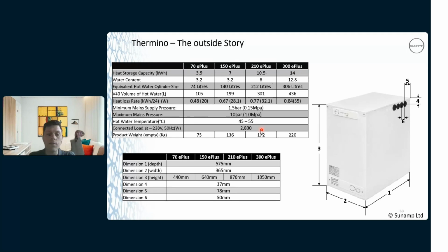Our units, I've got a 2.8 kilowatt element in the base here. So all units are the same, 2.8 kilowatts, which will be running about 12.5 amps. But when you take your charging times, it's just another question customers will ask you. You take the storage capacity and you divide that by your 2.8 kilowatts, and that'll give you your length of time in hours before you're at full capacity.